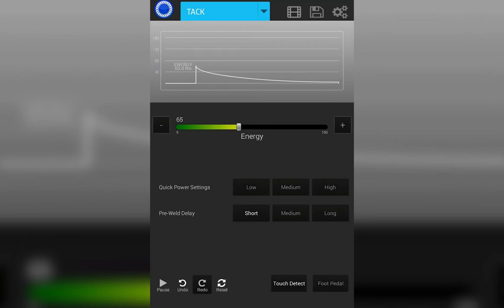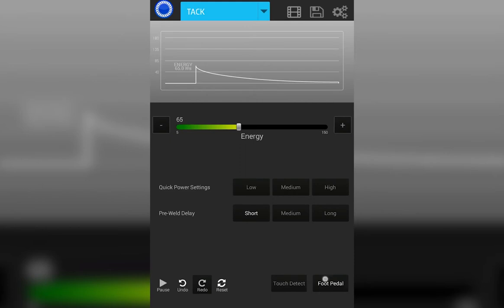Touch detect will initiate the weld as soon as the two pieces come in contact. Foot pedal will only begin the weld process once the foot pedal is pressed. For tack welding, we recommend to always use the foot pedal trigger option.